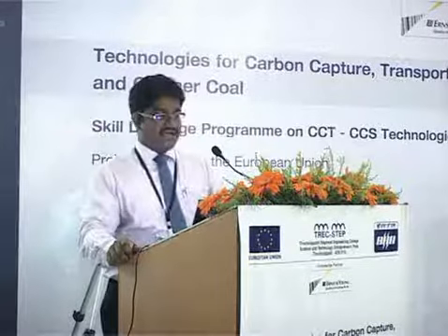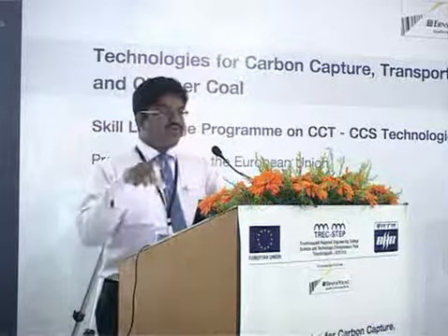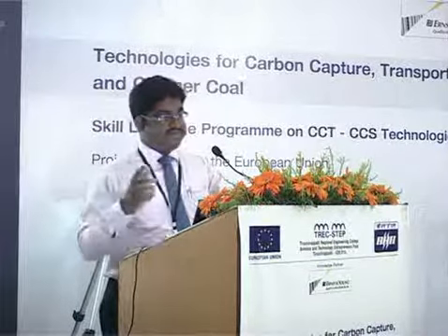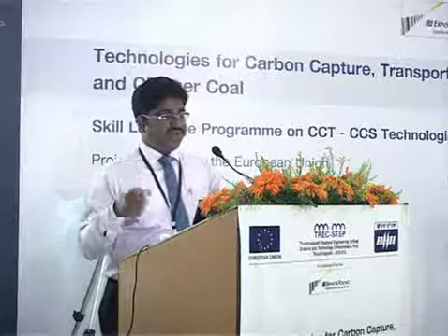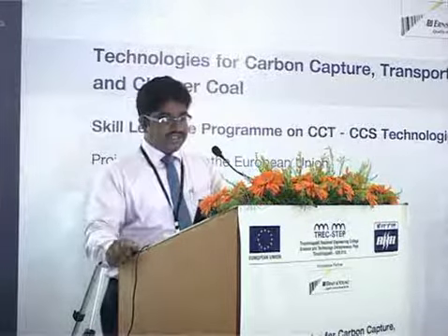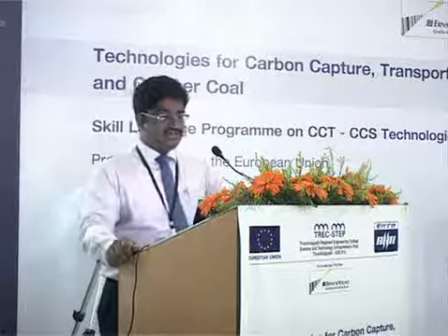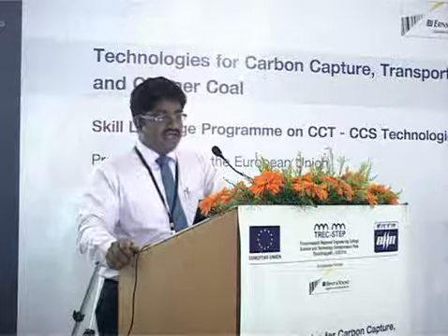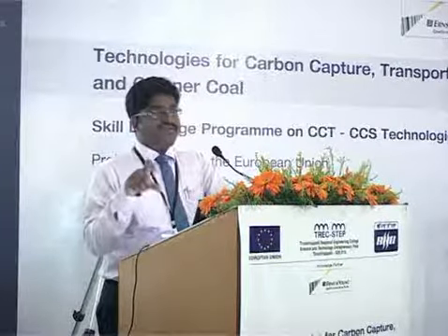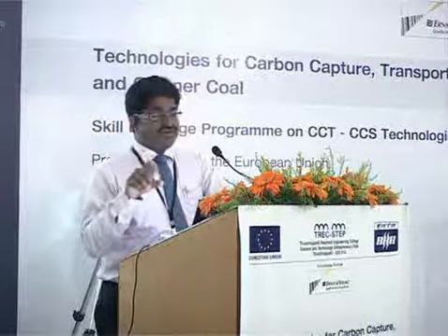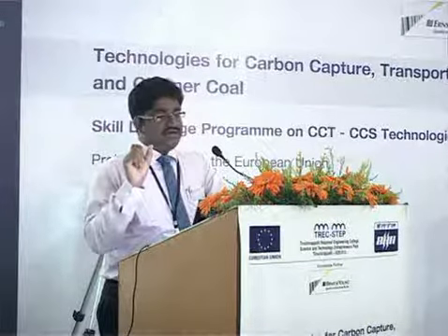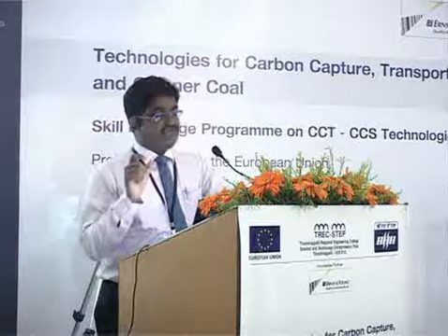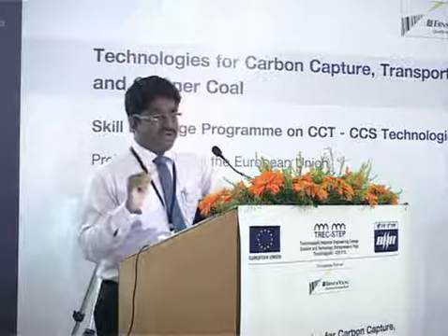You have seen the first slide. So they are going to do a retrofit in the steam turbines. They are going to do a retrofit. The rating is about 500 megawatt. It was designed in Russia and commissioned in China in 1996. Why are they doing the retrofit? They say they can reduce the specific energy consumption by 80 kilocalories per kilowatt hour.